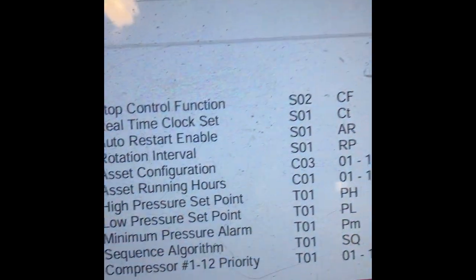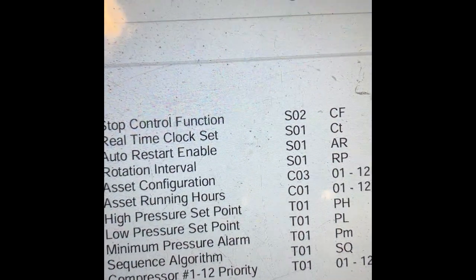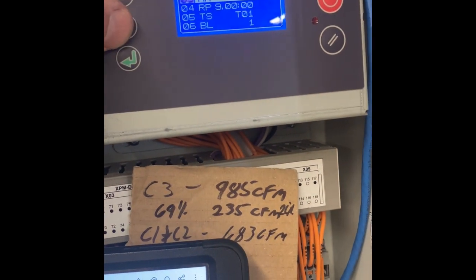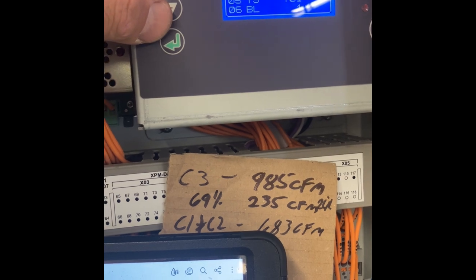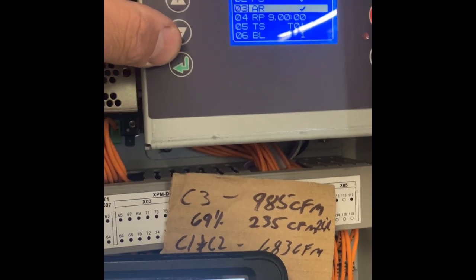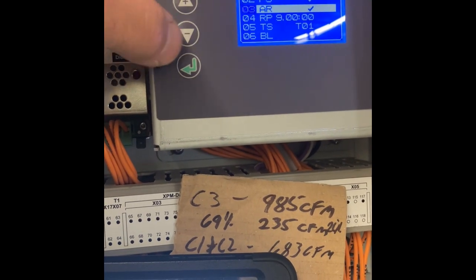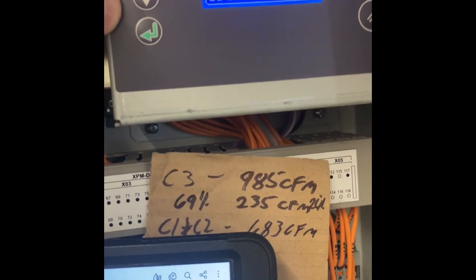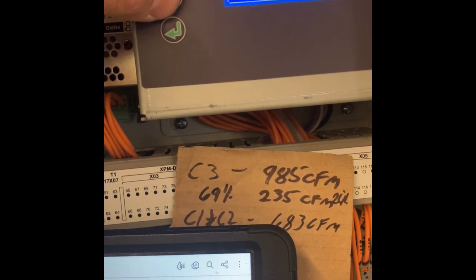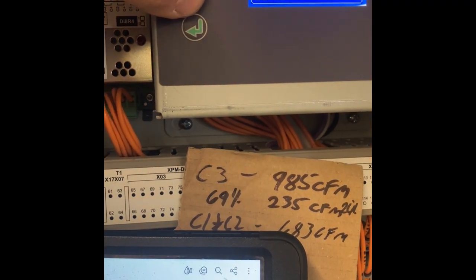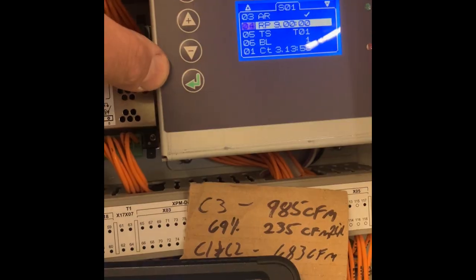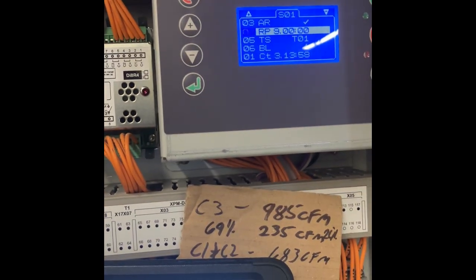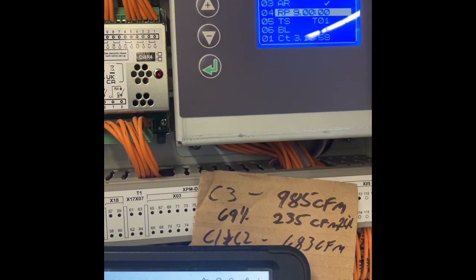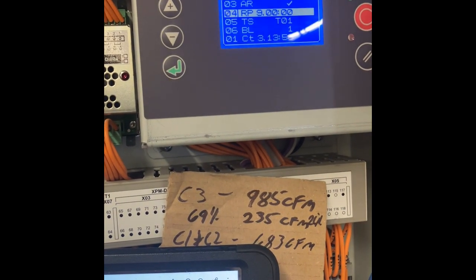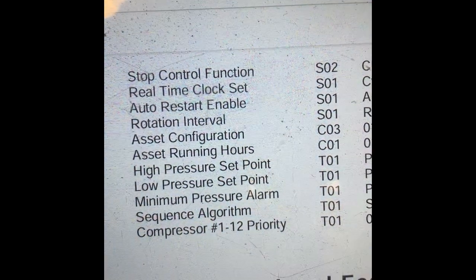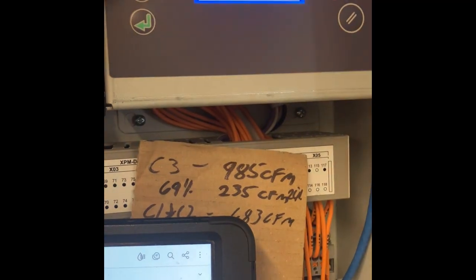The other one it wants you to set is auto restart. Again, you get a check mark or an X, and this is basically if there's a power outage, once power comes back on, the system will automatically restart. The PS is pressure scheduling, which we won't go over right now, but it is enabled. And then rotation interval, RP, that's in here somewhere. Yeah, RP. If we were going to rotate on a schedule or something, I would be more worried about setting that up. But we're actually going to go for efficiency running, so that RP is not going to be as important. So let's go ahead and go to C3 asset configuration.